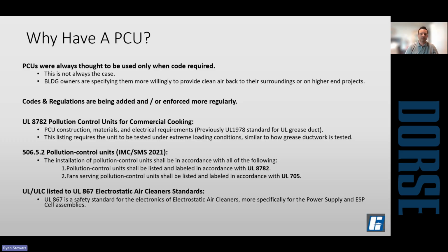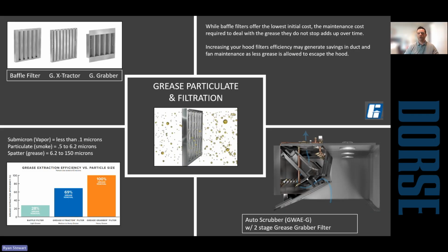And now you'll see in Chapter 506, which relates to exhaust fans, that they'll reference these UL requirements for pollution control units when they come up. And then there's a separate one for electrostatic precipitators. So pollution control application. If you have an application like this, the first line of defense is going to be your hood filters. The standard from Greenheck, we're typically going to go with an X-Tractor filter always. In most cases for a PCU, we'd stick with that same filter. It's something that's easy enough to maintain by the restaurant staff.